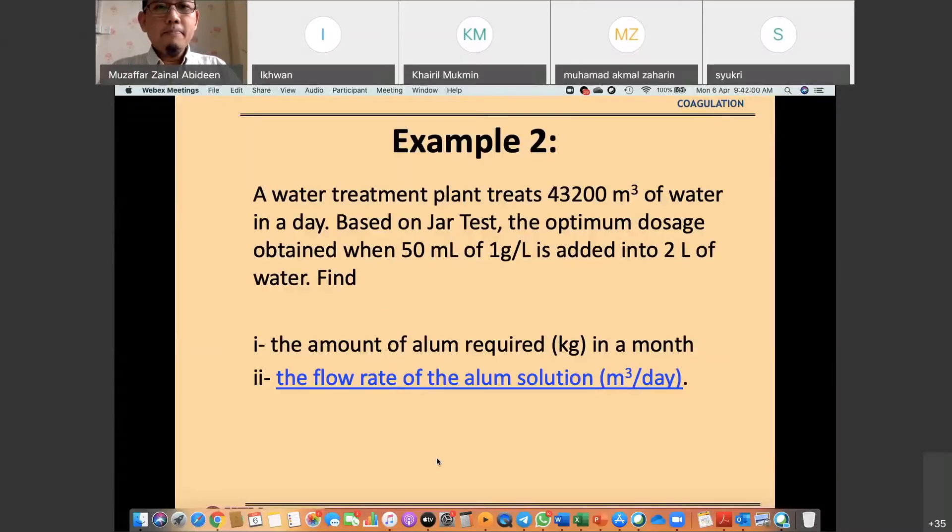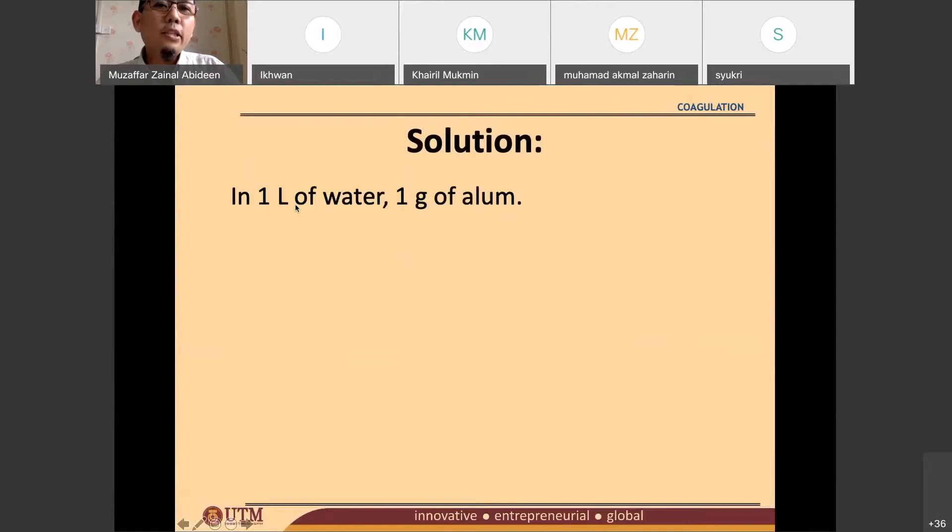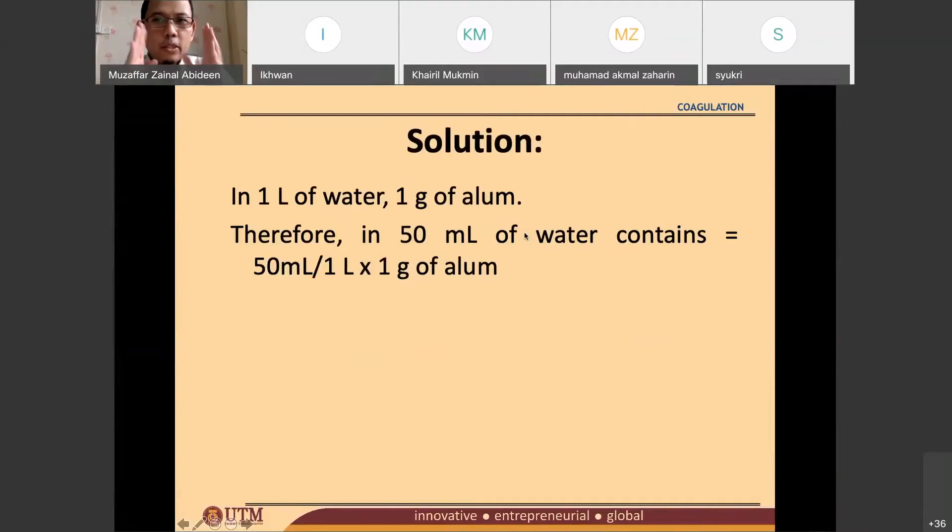So we like to know the amount of alum. 1 liter of water got 1 gram of alum. So we know that in 50 ml of water, the amount of alum need to be transferred into 2 liters of jar test. So 50 ml over 1 liter times 1 gram of alum. So the amount of alum being transferred is actually 50 mg of alum. This is simple mathematics. There's no rocket science in that.